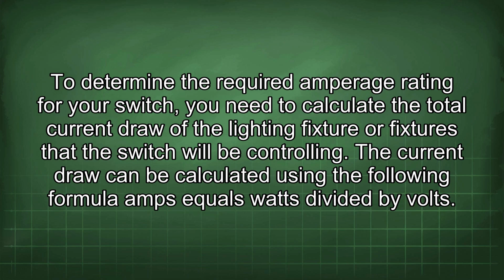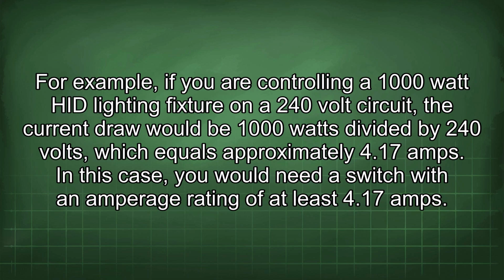The current draw can be calculated using the following formula: amps equals watts divided by volts. For example, if you are controlling a 1000 watt HID lighting fixture on a 240 volt circuit, the current draw would be 1000 watts divided by 240 volts, which equals approximately 4.17 amps. In this case, you would need a switch with an amperage rating of at least 4.17 amps.